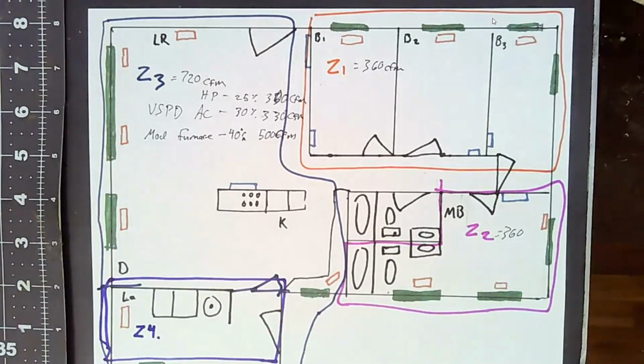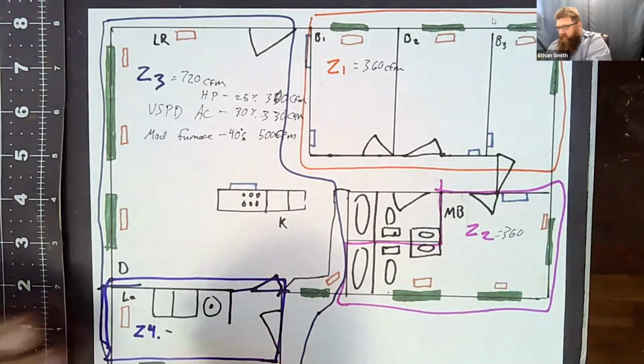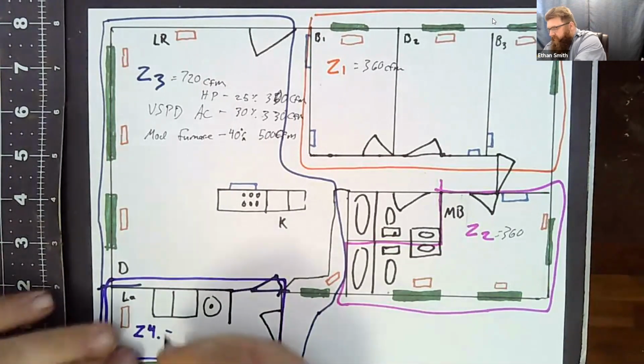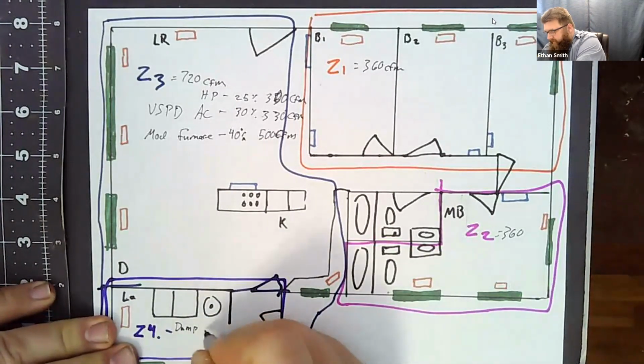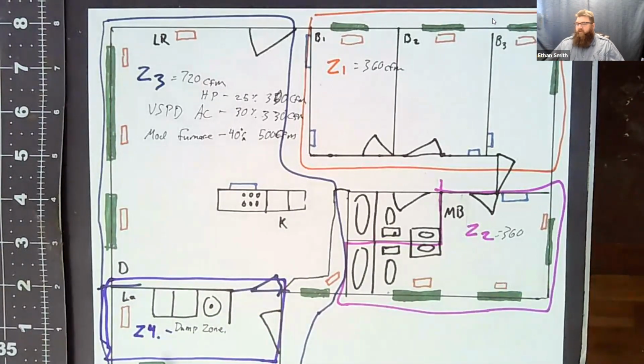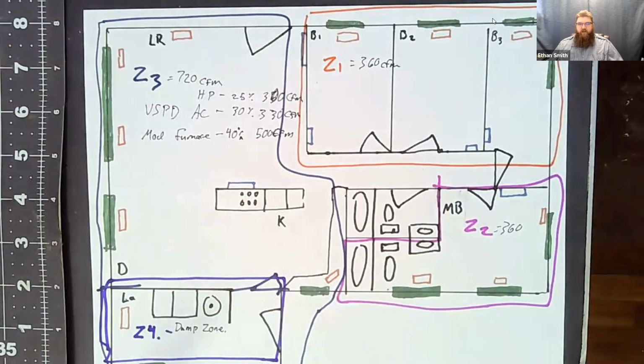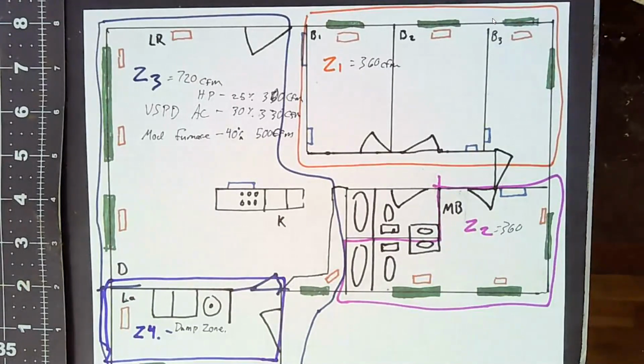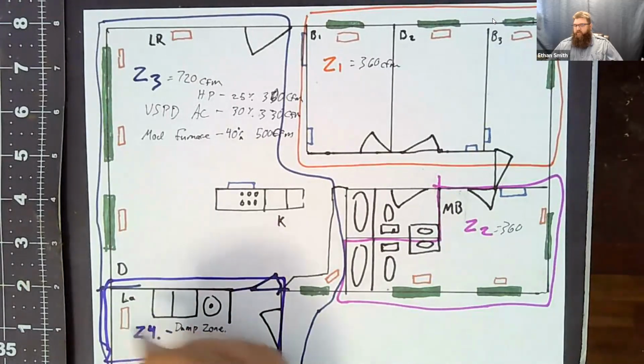You can make that as a bypass zone or a relief zone. Okay, so you could make this what we call a dump zone. This is where we put our excess air. So when we've got excess air in zone 2 or zone 1, we're going to take that extra 140 CFM and dump it into the laundry room. Just so happens my laundry room will take about 120 without building any static. So that'll probably work. Okay, what risk do we run when we do that? Overheating or overcooling that room. We could overcool or overheat this room if we use it as a dump.